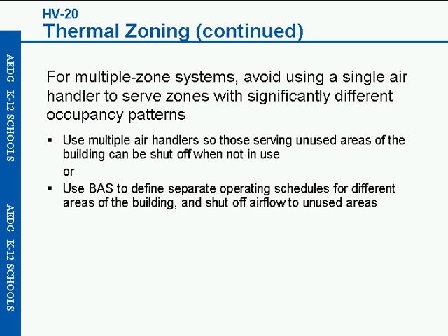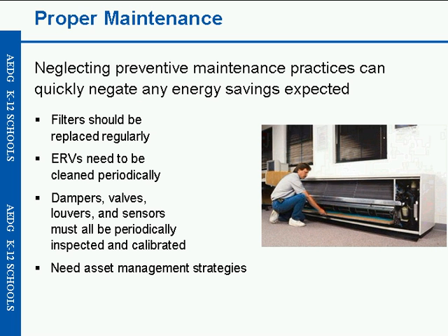And another important design tip is maintenance. Schools are notorious for neglecting maintenance programs, and neglecting preventative maintenance practices can quickly negate any energy savings expected. Things such as filters, ERVs checked and cleaned, dampers, valves, louvers, sensors must all be periodically inspected and calibrated, especially when it comes to CO2 sensors, as well as the asset management strategies, being able to manage your utility bills and verifying energy savings are continued and sustained.